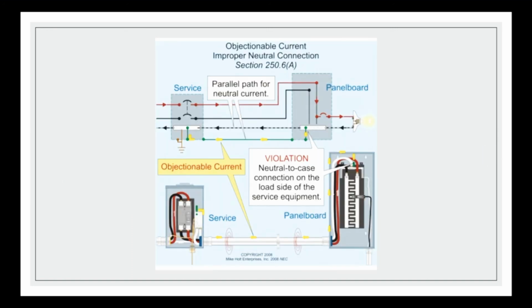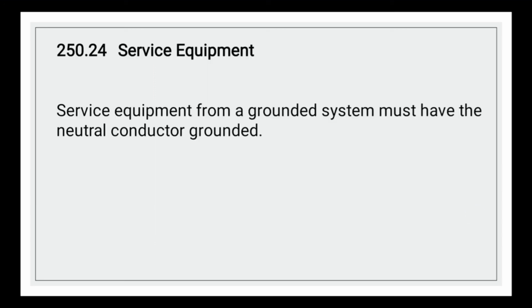Okay, this is an application of objectionable current due to improper neutral connection. Okay, the violation, where is the violation? Because we improperly made the neutral connection, the current flows from neutral to case on the load side of the service equipment. That's why we call it objectionable current.